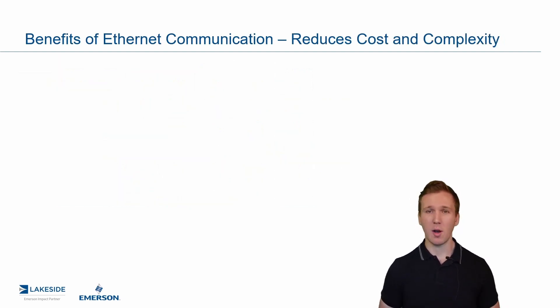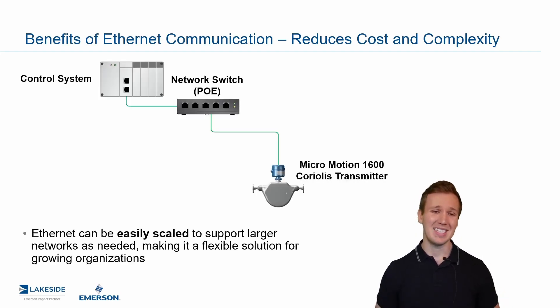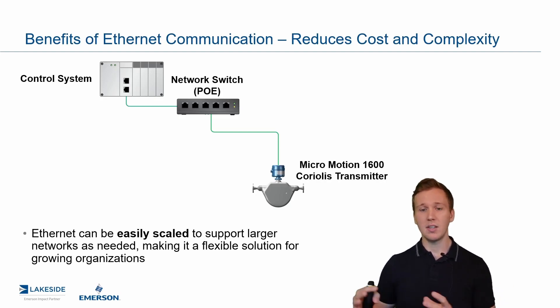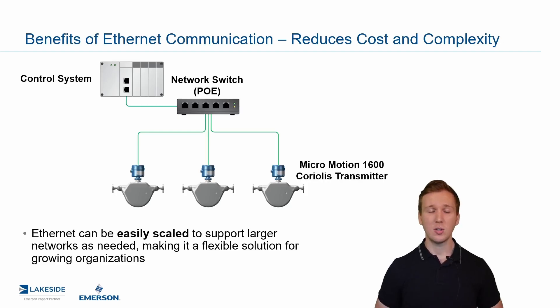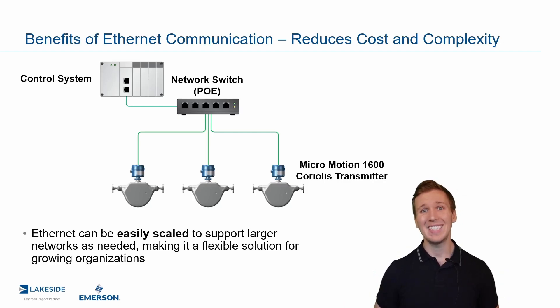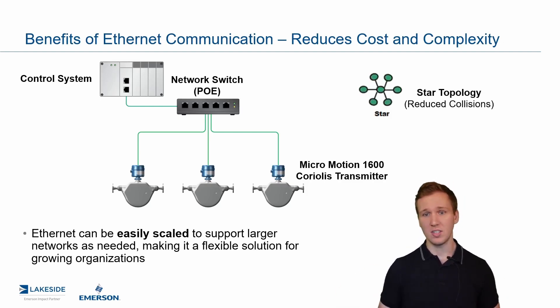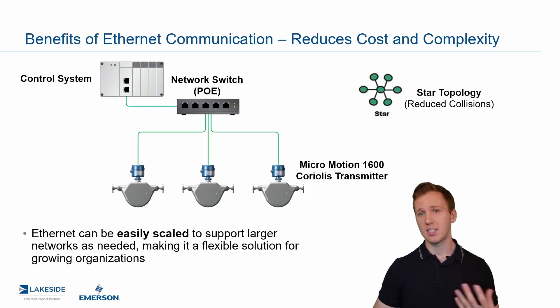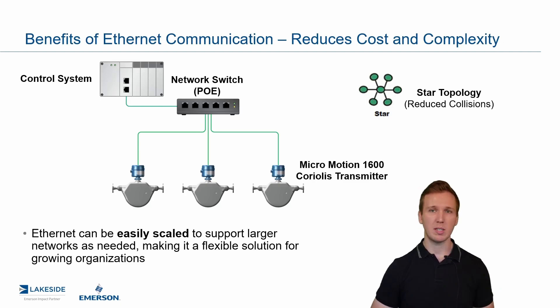The other piece is it just reduces cost and complexity. Ethernet networks can be very easily scaled. So if we have a typical system here where our network switch is providing power to our Coriolis transmitter — maybe we're monitoring flow or density on one line — if you wanted to add in an additional two sensors, you would just add them in, connect up to that same network switch via the Ethernet cable. The wiring is a very simple process, which saves time and ultimately reduces the complexity and cost. We utilize what's called a star topology in terms of how the formation is, so the transmitters just connect right back to that network switch or power sourcing equipment. This aids in reducing complexity compared to other topologies such as ring or point-to-point.